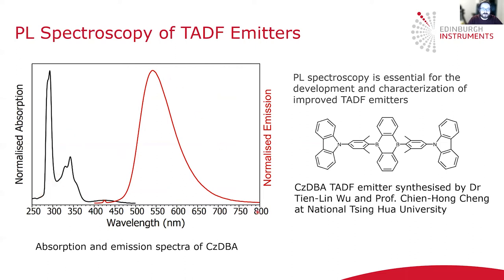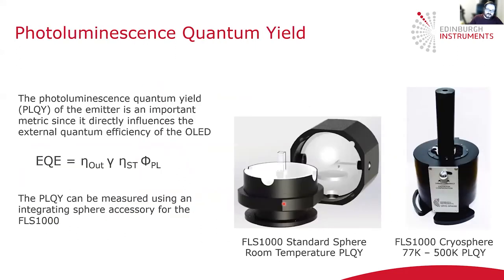For simple spectral measurements, the absorption and emission spectrum can be measured. More importantly, the photoluminescence quantum yield can be measured using the FLS1000. The photoluminescence quantum yield tells you how efficient the emitter is — it's the ratio of the number of photons emitted to the number of photons absorbed. This is crucial for developing high efficiency OLEDs because the external quantum efficiency of the OLED is directly proportional to the photoluminescence quantum yield.